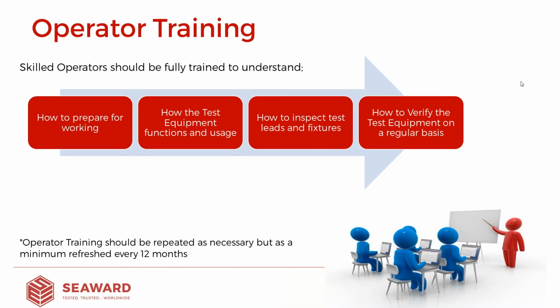Before we get an operator out performing the testing, there are four main sections of things that they really should understand. And I'm going to break this down into two sections of two, really. Those that all operators should understand, and those that the skilled or supervisory level people should really be understanding. So we're going to talk about how they should prepare for working, the kind of things they should be looking for, how the equipment functions, what usage they're going to do from the functions, do they understand exactly what they're doing during the tests, how to inspect things like test leads and fixtures at regular periods, and finally how to verify the equipment on a regular basis just to make sure it's doing its job correctly.